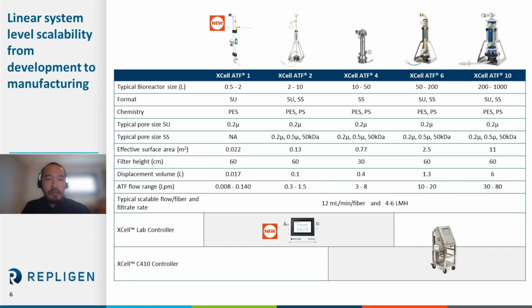Also notice that the filter length is 60 centimeters, so this is the same as ATF2, ATF6, and ATF10. And this is for the main purpose of linear scalability, to enable this reliable scale down model down to at least 500 mils and possibly even less. Each ATF device here is controlled by a controller. And of course, each controller supports a number of ATF devices.